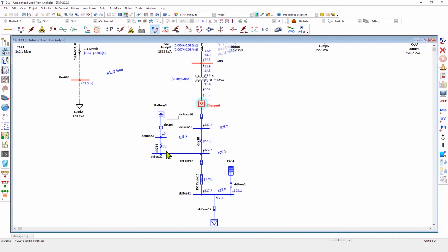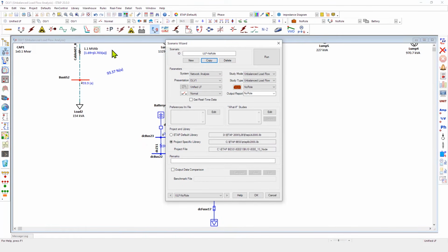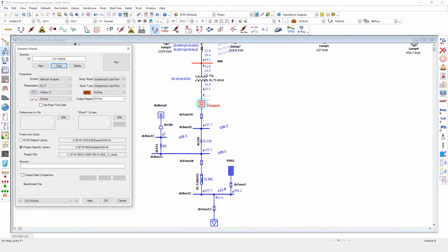In this case, we can observe that the majority of the PV array power is being delivered through the rectifier into the AC network, and the battery is not charging nor discharging based on the BMS settings. We can then simply switch over to another case where we increase the DC load in our network. When the DC load is increased, you can see the power change on the DC load, and this battery is now delivering additional power into the DC circuit, and the power contribution or the injection into the AC network is reduced.